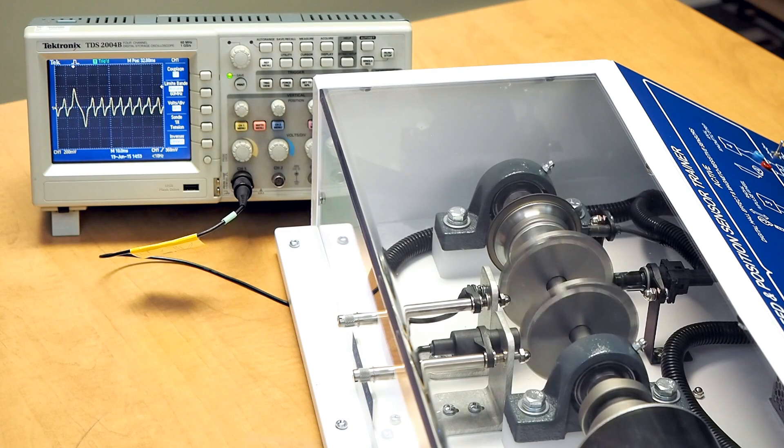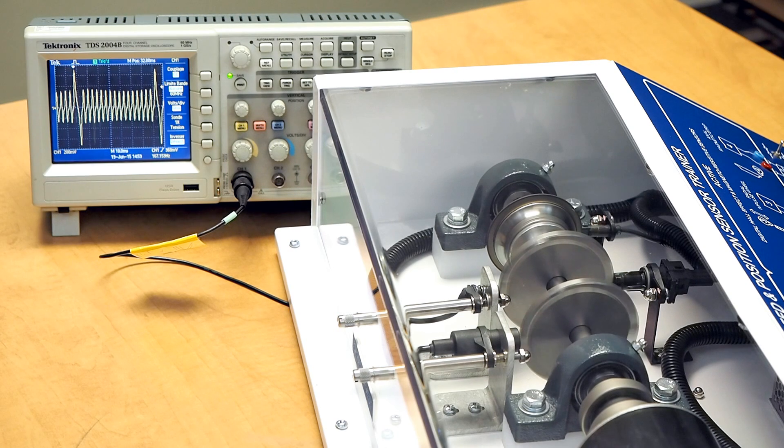Here we can see a textbook pattern for an inductive speed sensor. Now by changing the speed on the shaft, we can see changes in amplitude as well as frequency.